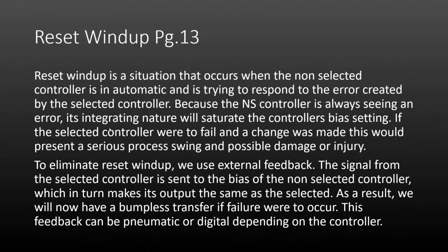Reset windup is a situation that occurs when the non-selected controller is in automatic and is trying to respond to the error created by the selected controller. It's there waiting to do its work, pretending to do its job, but the other controller is actually doing the job. Because the non-selected controller is always seeing the error, it's reading the process the same way as the selected one, but it can't change its values because it's not selected.